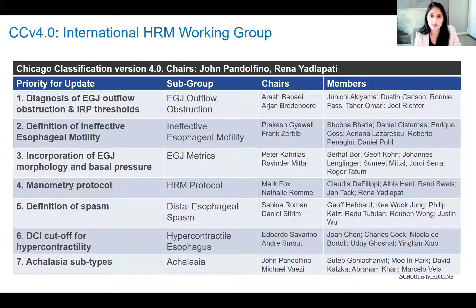So now in Chicago 4.0, there is flexibility that the protocol can start in either a supine or an upright position, but it does recommend that both positions are utilized. So if you were to start in the supine position, the recommendation is that first there's a 60-second adaptation period. And then the patient is recommended to take 3 deep breaths, and that's to confirm the catheter placement, ensure that the catheter tip has traversed the crural diaphragm. Then there's a 30-second baseline period. And during this time, we can identify landmarks, assess the EGJ morphology, including the EGJ contractile integral, intragastric pressure, baseline EGJ pressure. Then start the test swallows with 10 5-milliliter wet swallows.